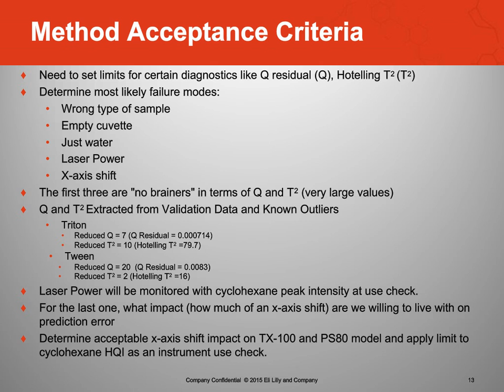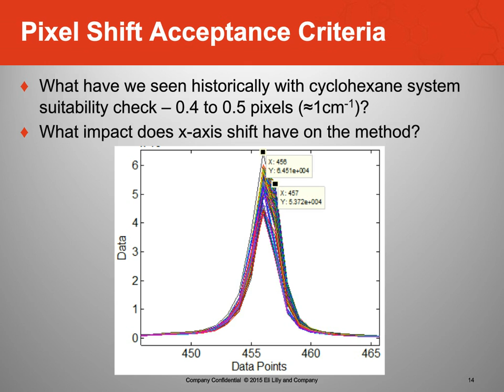So cyclohexane, during the course of developing both the calibration model and doing the validation, we generated quite a number of cyclohexane runs. And I noticed that for all practical purposes, the highest peak was around, and this is in pixels, around 456. However, there was a small shoulder at 457, and in some cases, some of the runs did not show that shoulder. So it kind of showed me that there may be a shift of a peak, and if you just extrapolate or infer where it might be, it could be anywhere between 456 and 457. So I said, we're probably looking at about a half, 0.4 to 0.5 pixel shift, which is equivalent to about one wave number. And again, how does this impact the model?